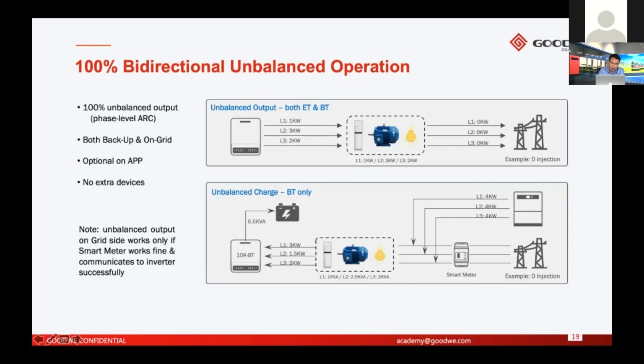Okay, and 0 kilowatts on phase 1 and 3 kilowatts on phase 2, they can realize at the same time. It's not separate time. It's the same time they can realize. So this is what we call unbalanced output. The same logic applies on the charge; unbalanced charge is the same. And another one is that both on the backup and on-grid sides, we can realize unbalanced output.